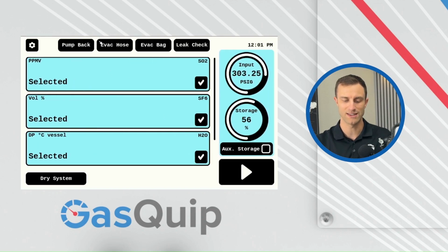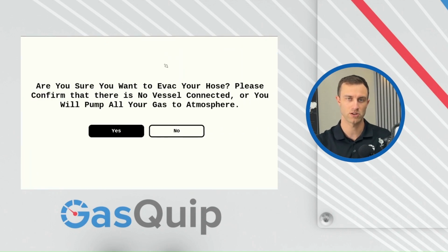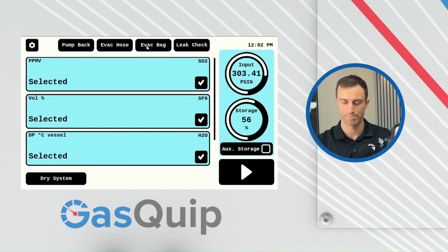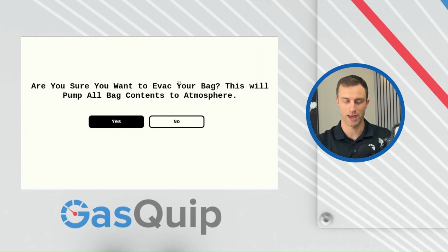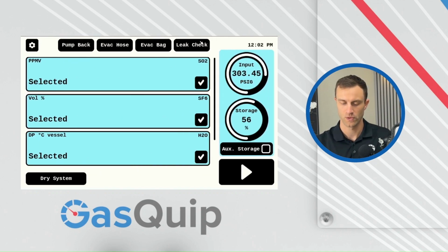You can also do an evac hose here from the home screen like we did earlier, and that's going to pull an evacuation on the hose or any fittings or any regulators that are hooked up to the end of your sample hose. We can run an evacuation of bag if you've run a flush system with nitrogen, just to flush out your system with pure nitrogen, or if it's appropriate to do so with SF6, you can evacuate all of the internal storage to atmosphere.